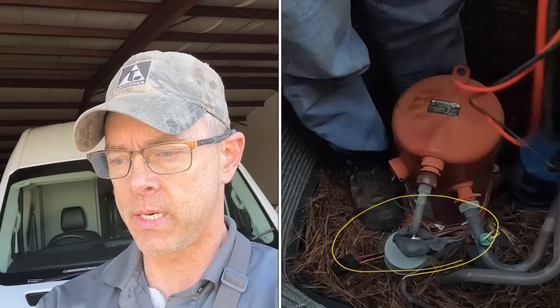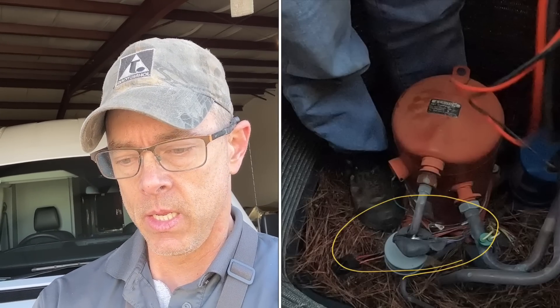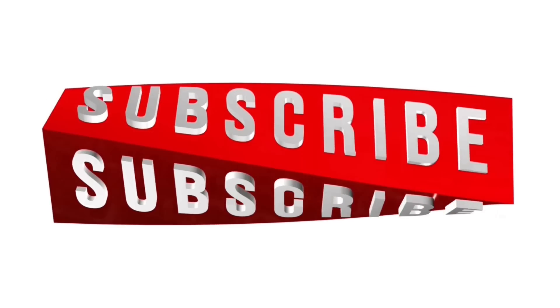Okay guys, what I was having trouble explaining and showing at the time — it was getting dark, my camera was giving me trouble — and replacing the contactor: the contactor was burnt from it chattering like that, so it was not a waste of a part. The thermistor or temperature sensor should be on the way soon. I hope you enjoyed that video — like and subscribe if you haven't already, and I'll catch y'all in the next one. Bye.